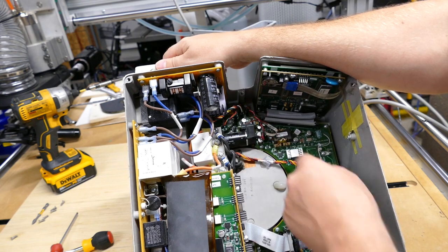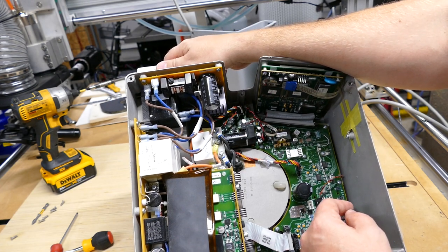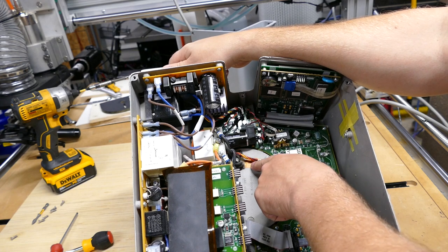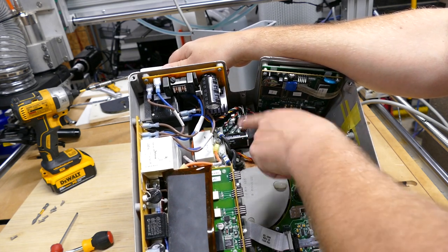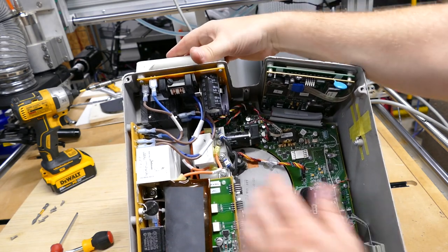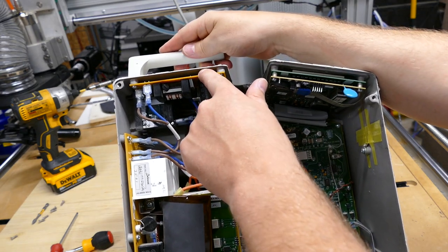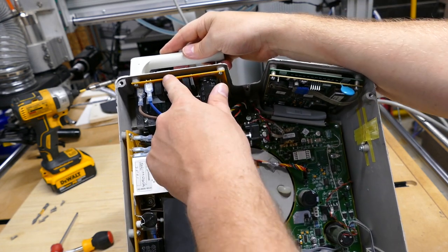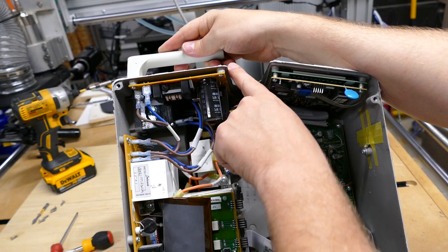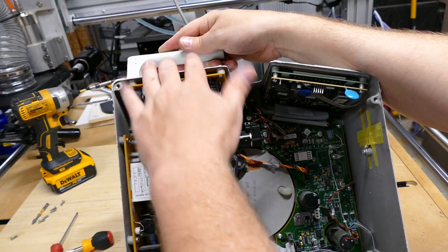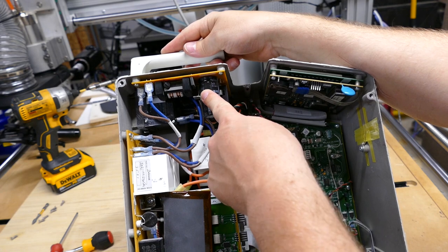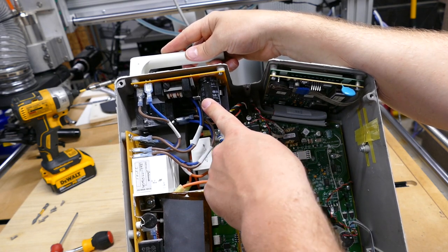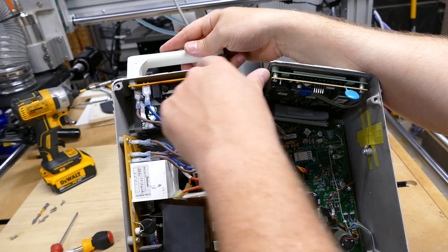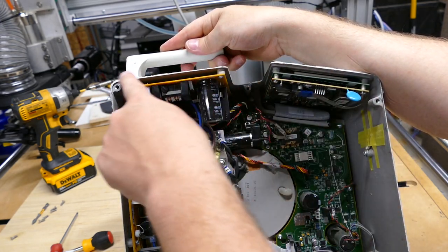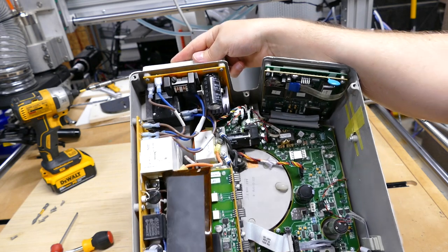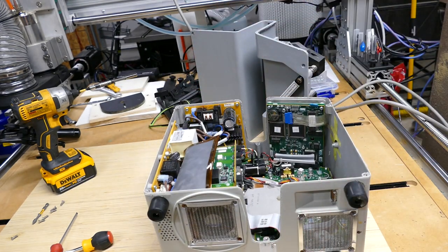This little guy right here is the motor that is controlling that peristaltic pump. You see the coils right here that come to the induction heater? They come up to a distribution block. One of the things that you'll have to worry about is right here. Look at this card if you ever open this up and look for signs of fluid damage. Because if this seal up here around the top ever develops a leak, you will get fluids that will seep in right here on this board and it'll make this board pretty much explode. So be wary that this is the most important surface of this entire unit to make sure it's sealed. And that is pretty much the inside of this unit.